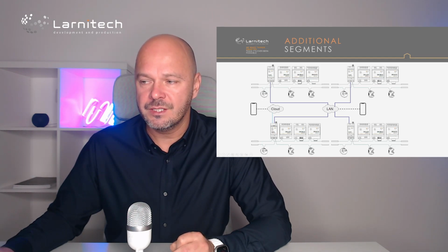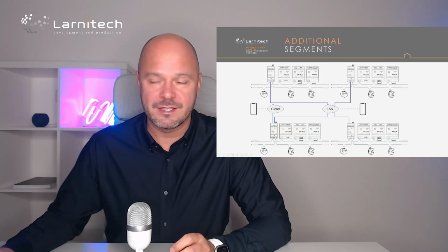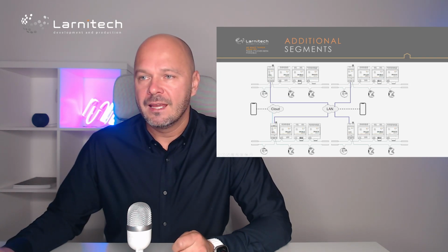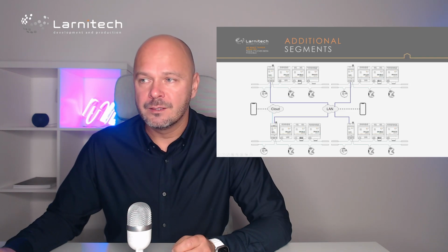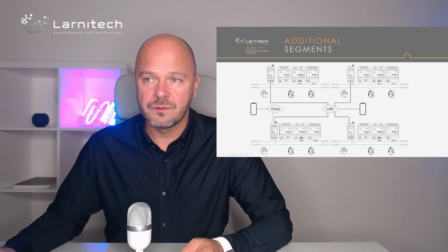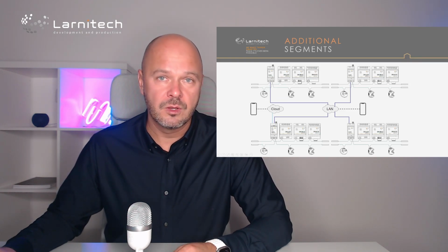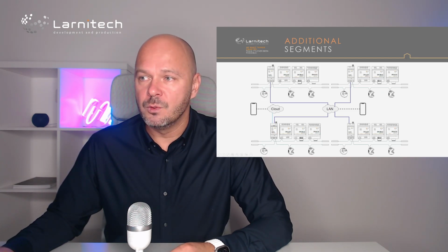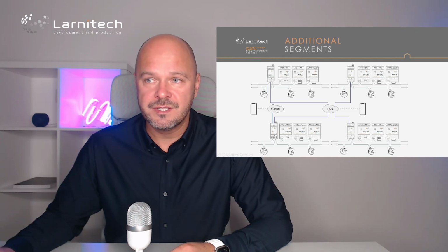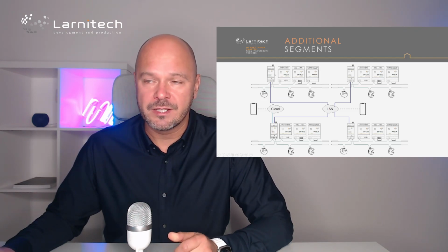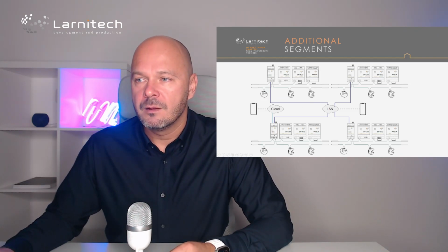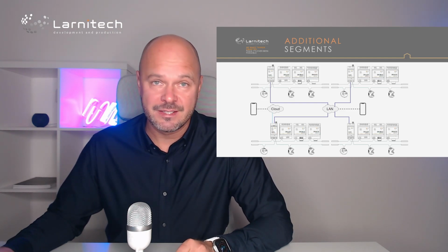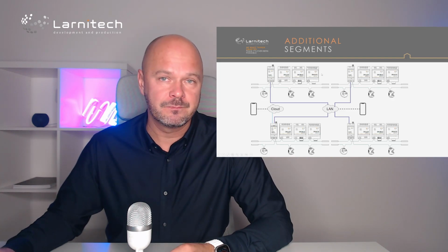So DEGW gives you 2 more buses, and then 2 more, and then 2 more, and so on, until you reach the capacity of your local area network. So you can connect maybe a few hundred of those DEGW gateways, but not more than 999 devices in the whole system.